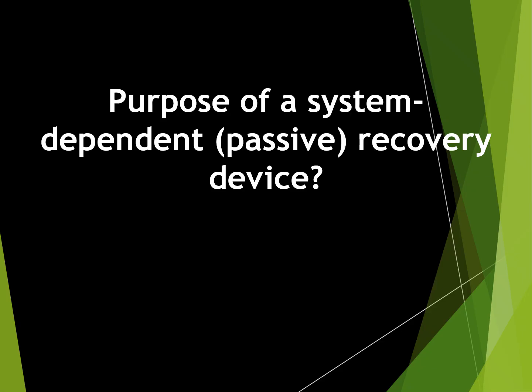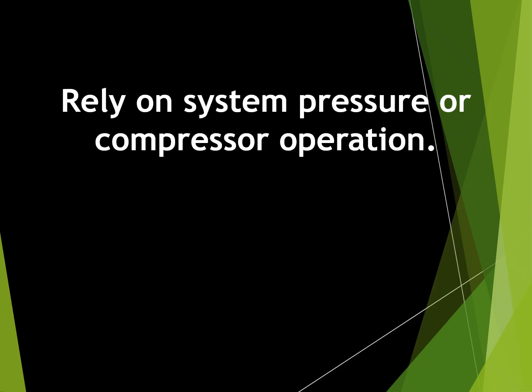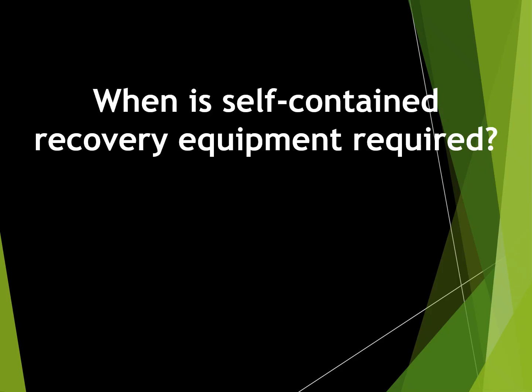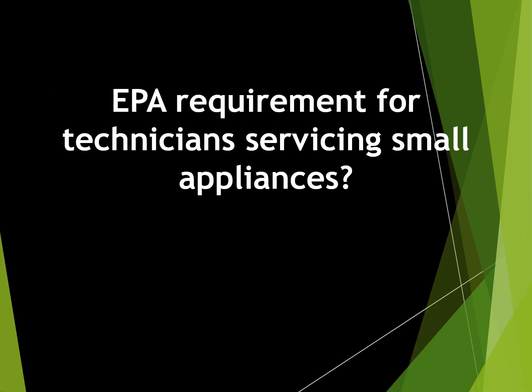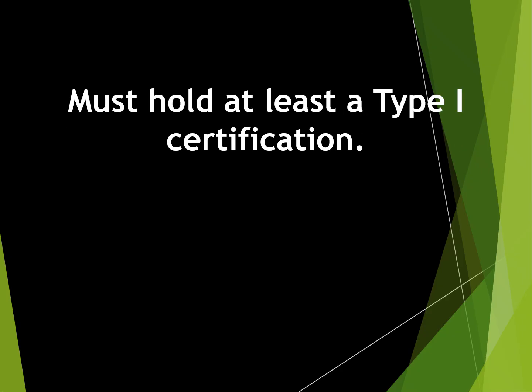Purpose of a system-dependent passive recovery device. Rely on system pressure or compressor operation. When is self-contained recovery equipment required? When the compressor is not operational. EPA requirement for technicians servicing small appliances. Must hold at least a Type 1 certification.